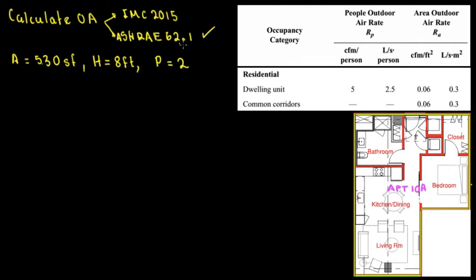So for ASHRAE 62.1, the equation to calculate the outside air equals to the following. Outside air equals to the RP times PZ plus RA times AZ, everything divided by the distribution effectiveness EZ. And also, if we're following the ASHRAE nomenclature, which is how they represent area, how they represent rates. So this is pretty much ASHRAE nomenclature.